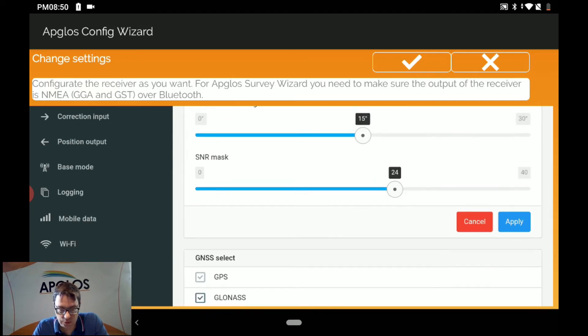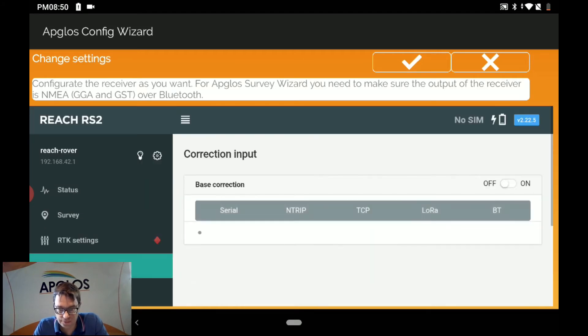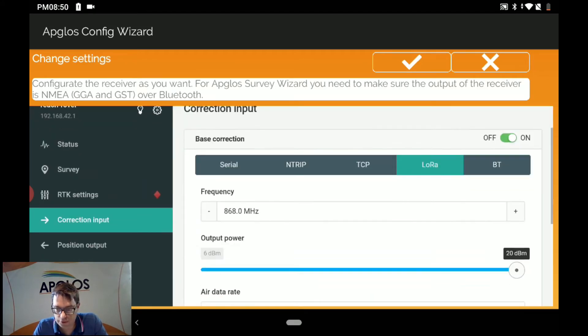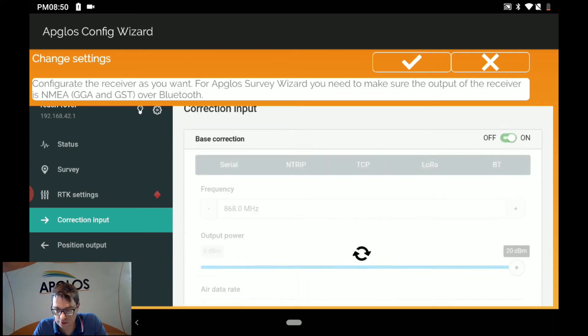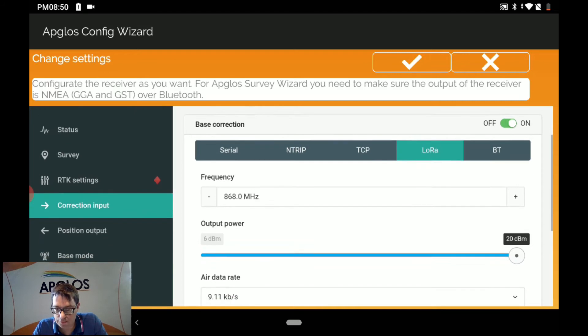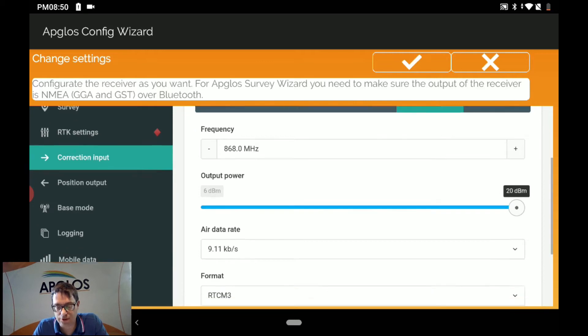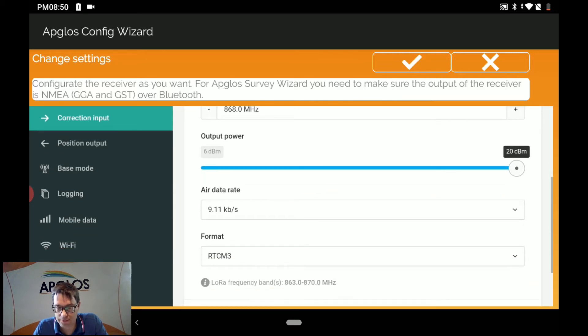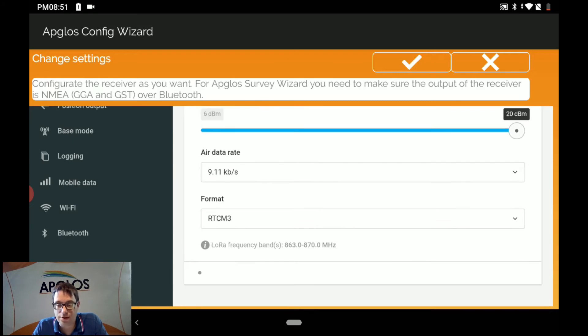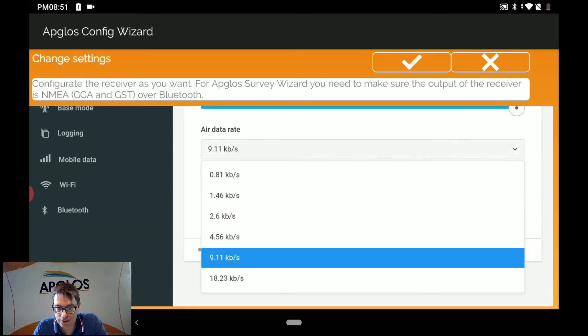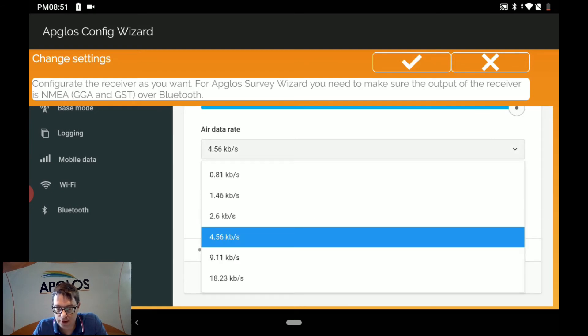Then we go to the correction input. And we make sure that there is the base correction. We select LoRa. Then you have to make sure that the frequency is the same as in the base. In this case, it's already the same. The output power has to be 20 dBm. The air data rate has to be 9.11. If you change this, then you have to click apply.